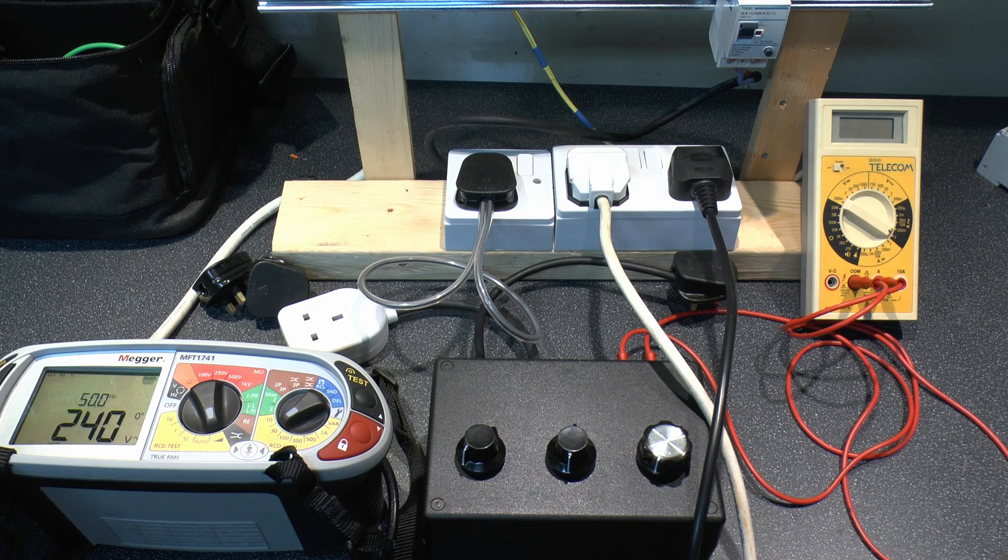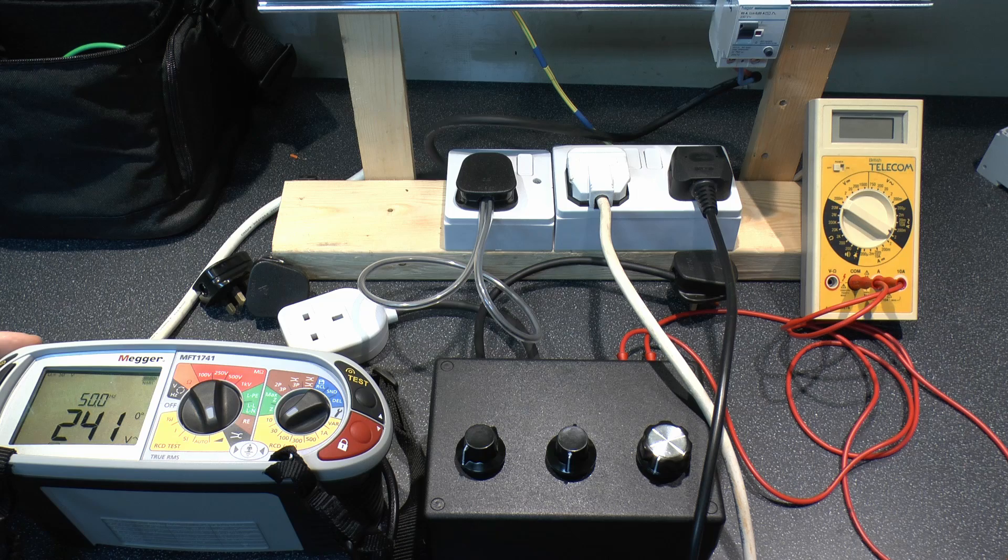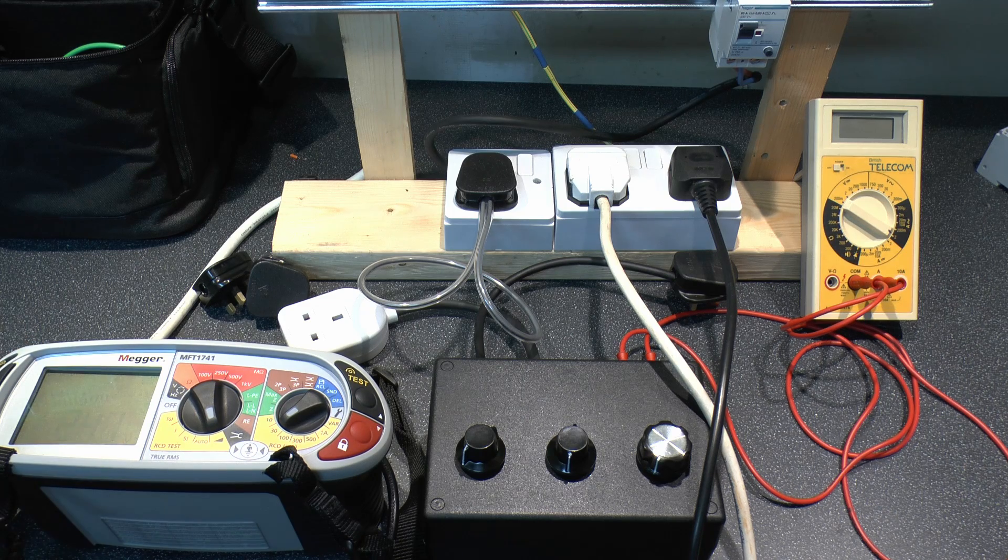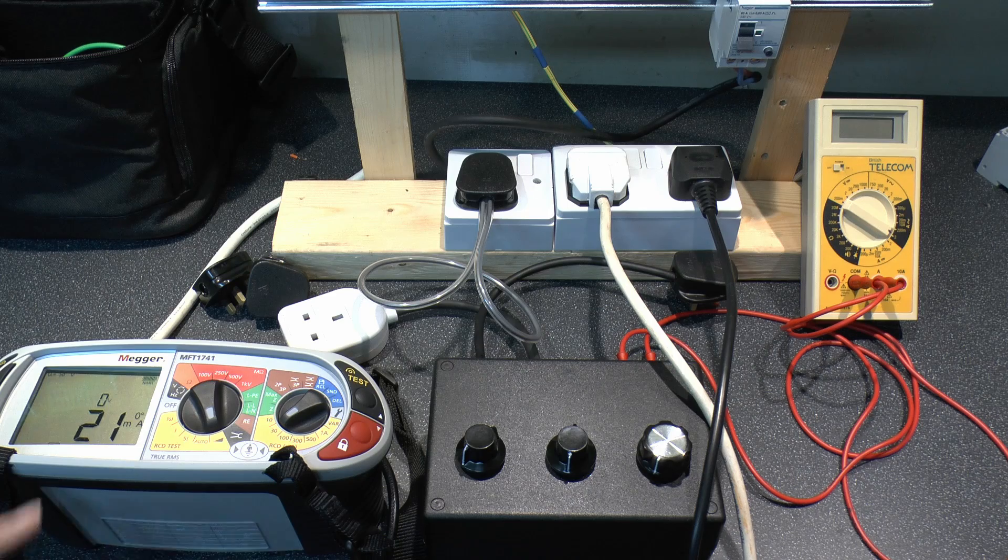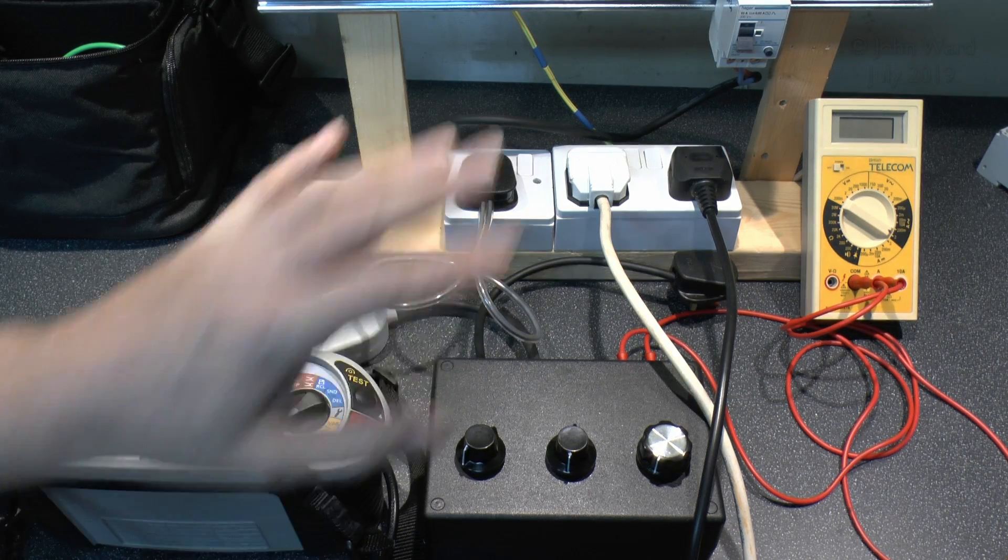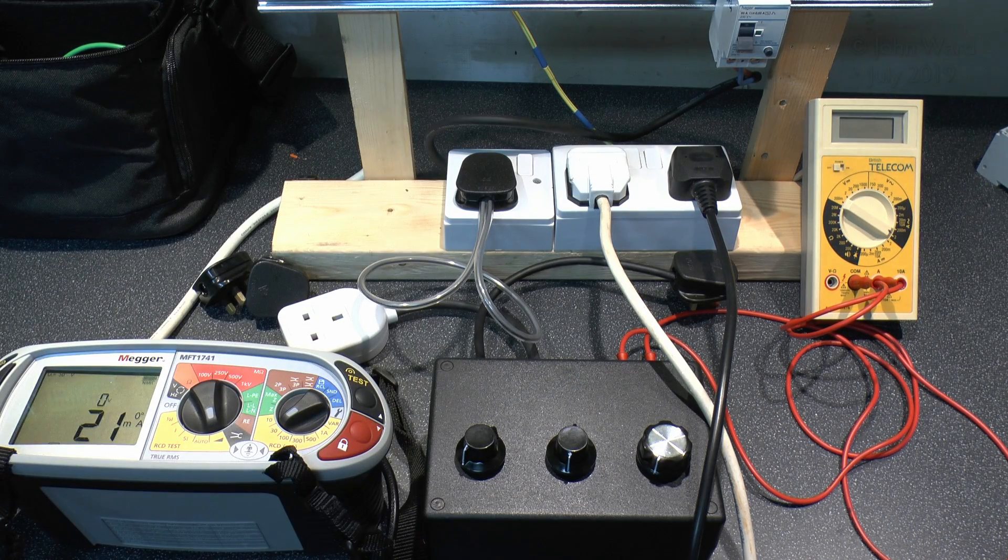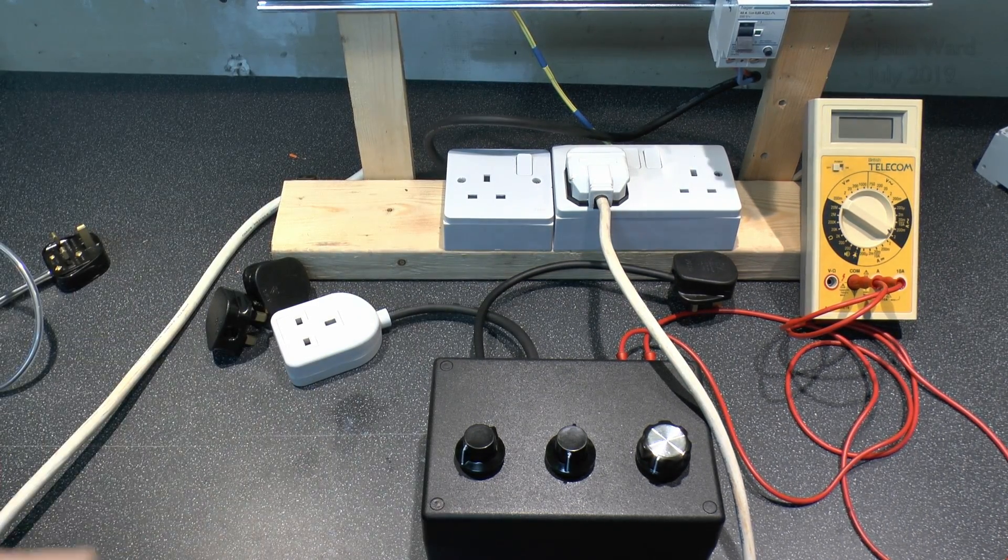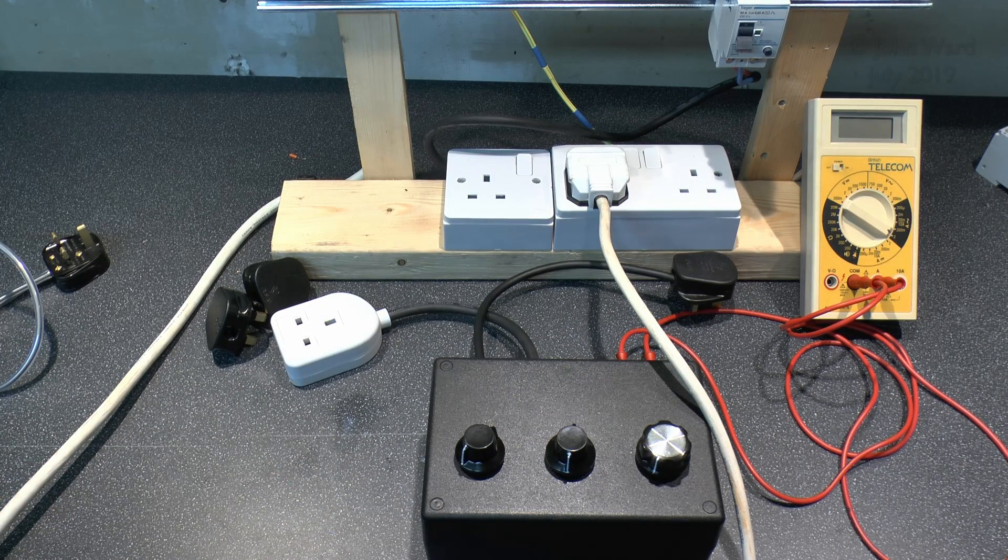So we're just doing the ramp test here so just press the testing button and see what the current trips at actually is. So it just takes a moment. So currently 21mA so that's perfectly within specification of the device so again no problem with that. Now the purpose of that test was just to confirm that what we've got here is reasonably consistent with what we've just tested there.